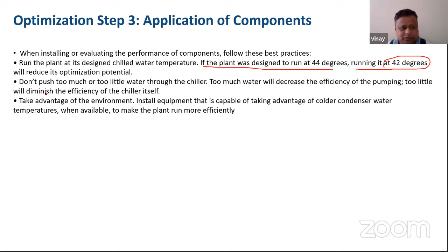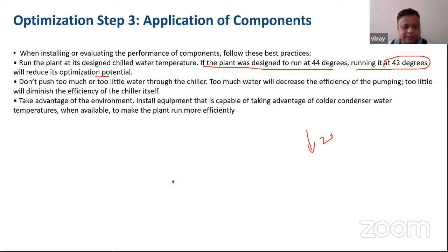If a plant was designed to run at 44 degrees, running it at 42 degrees will reduce the optimization potential because you're reducing by 2 degrees. When you reduce by 2 degrees, the chiller will not be too loaded, and we can save some energy. Then there's automation of the system, and that's why BAS and BMS come into the picture, where we can do a lot of detailing.